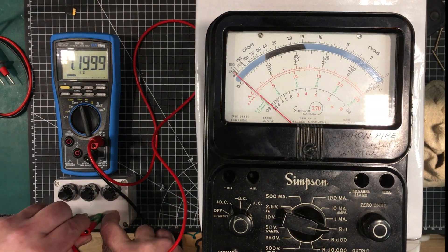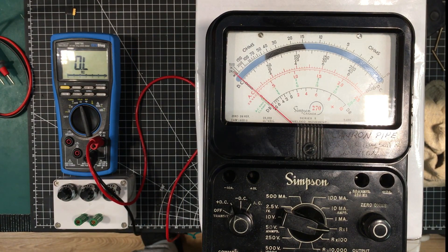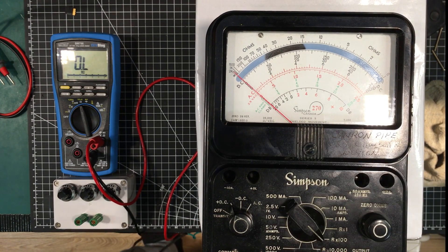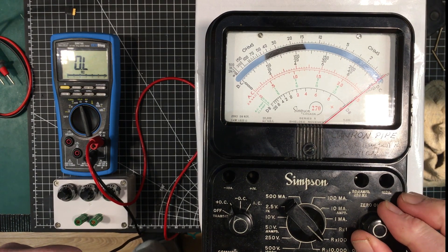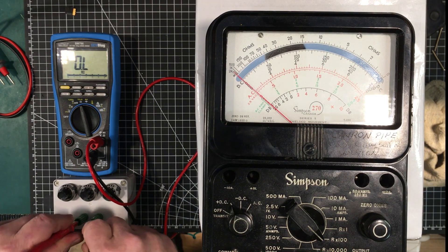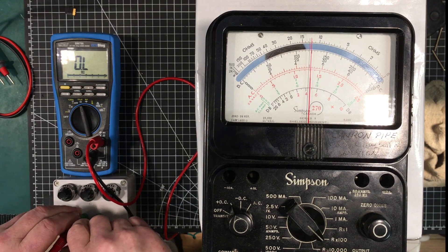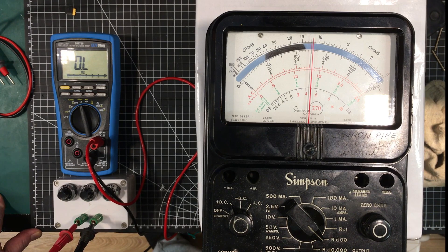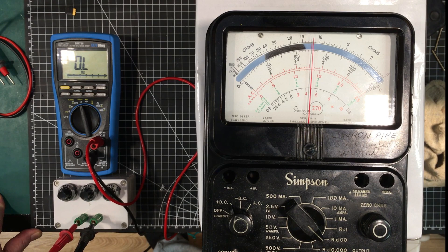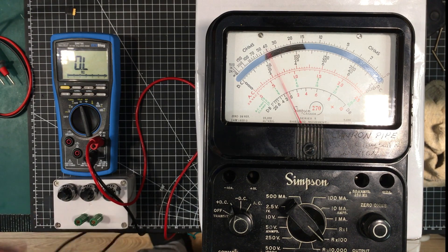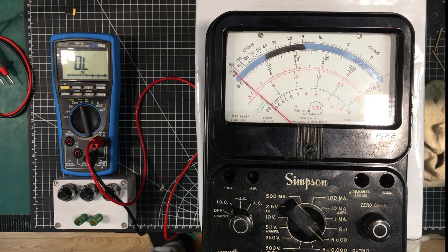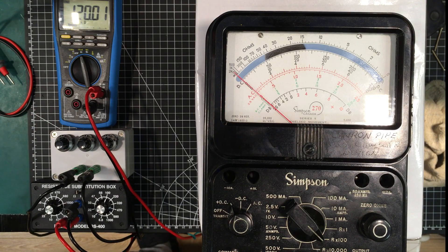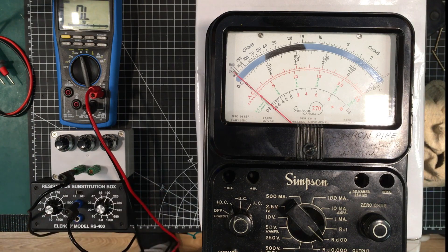Let's get 1200 ohms. We're supposed to be between 1130 and 1260. Let's zero this range out.